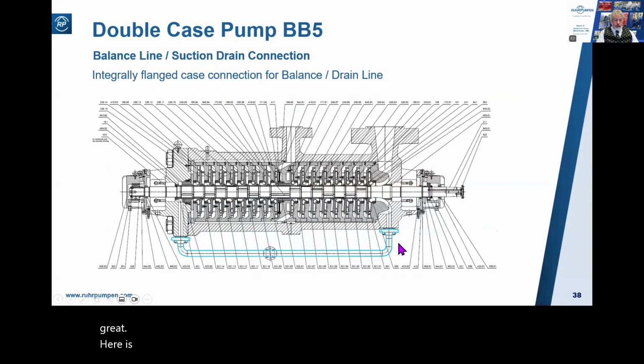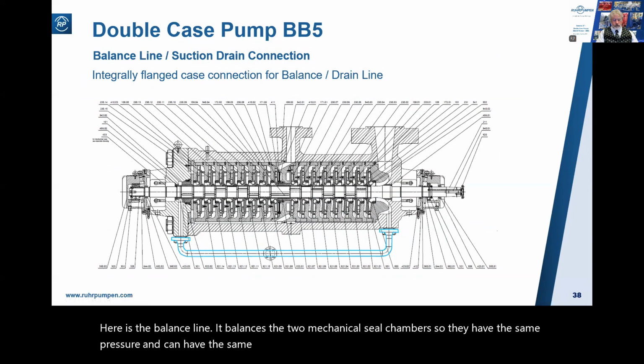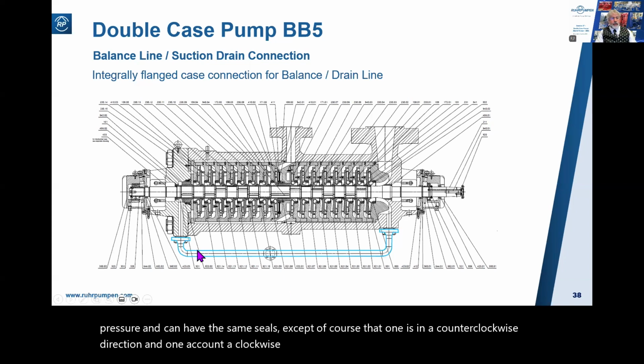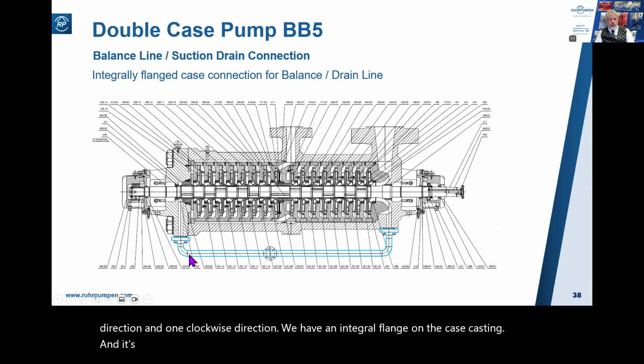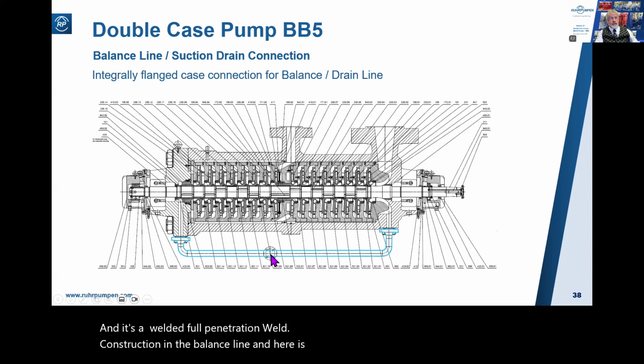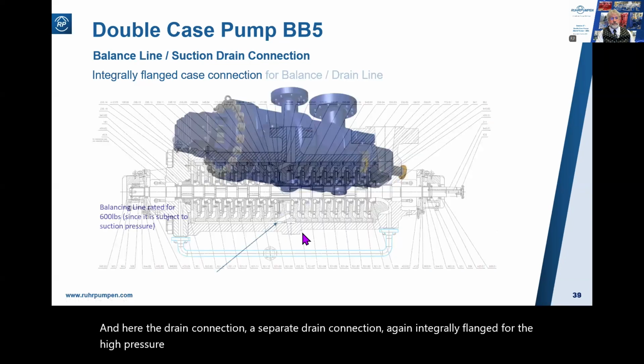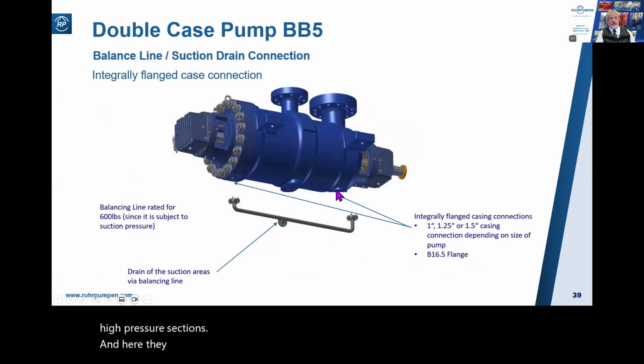Here is the balance line. It balances the 2 mechanical seal chambers so they have the same pressure and can have the same seals, except of course that one is in a counterclockwise direction and one a clockwise direction. We have an integral flange on the case casting, and it's butt welded, full penetration weld construction in the balance line. And here is the drain connection for the low pressure areas of the pump. And here a separate drain connection, again integrally flanged, for the high pressure sections. And here they are in this picture, integral flanges. And here the balance line.